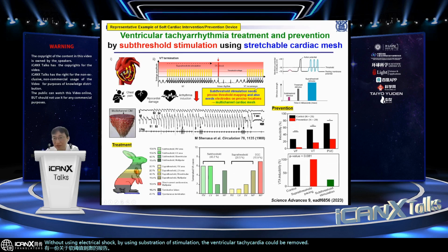Let me explain the concept of subthreshold stimulation first. There is a threshold voltage to modulate the beating of the heart. If the voltage of the electrical stimulation is higher than this threshold voltage, then we can modulate the heart motion. Of course, capture pacing should use a higher voltage, and electrical shock should use a much higher voltage than the threshold voltage. But subthreshold voltage stimulation means the voltage is lower than the threshold voltage. That means although we apply stimulation, and a very small current flows, the natural motion will be maintained rather than modulated. And that small current can remove VT. And since the current is very, very small, chest pain and myocardial damage can be prevented.